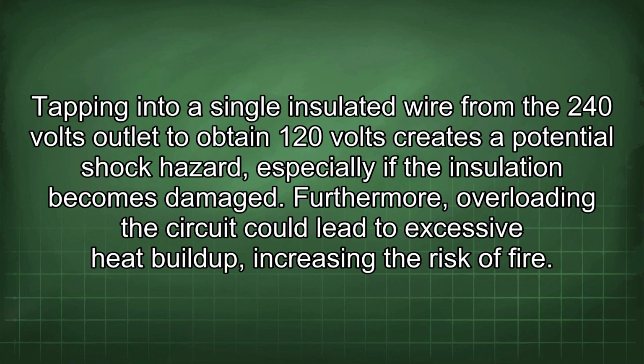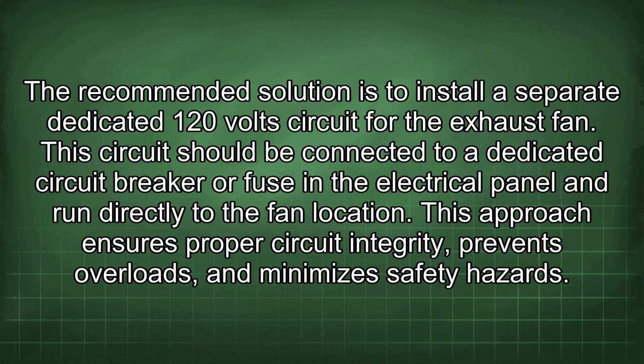Tapping into a single insulated wire from the 240 volts outlet to obtain 120 volts creates a potential shock hazard, especially if the insulation becomes damaged. Furthermore, overloading the circuit could lead to excessive heat buildup, increasing the risk of fire. The recommended solution is to install a separate dedicated 120-volt circuit for the exhaust fan. This circuit should be connected to a dedicated circuit breaker or fuse in the electrical panel and run directly to the fan location. This approach ensures proper circuit integrity, prevents overloads, and minimizes safety hazards.